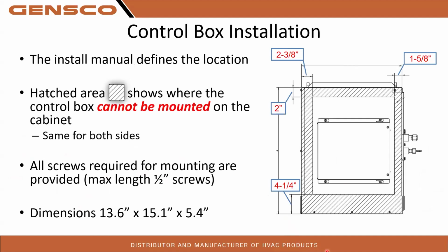Control box installation. If you are mounting the control box to your coil, there is a go, no-go zone. You'll find this in your installation manuals. The little striped section here is where you do not want to put any screws. You run the risk of hitting drain pans or anything like that. Yeah, that's for that PAA coil.